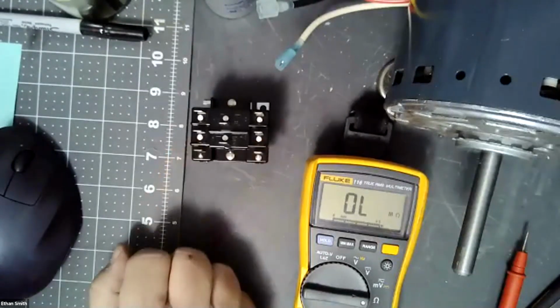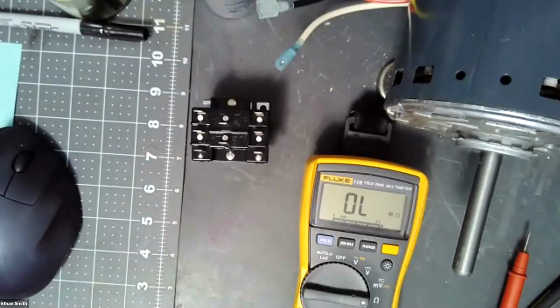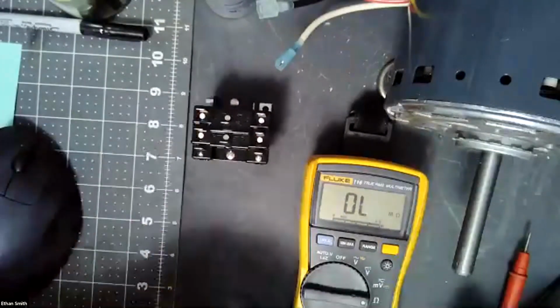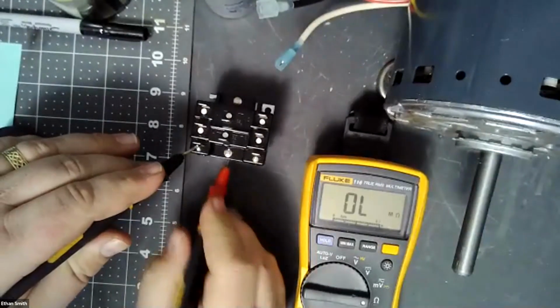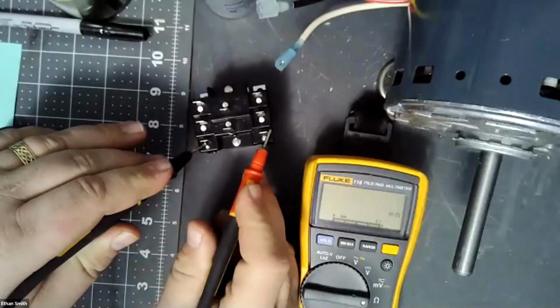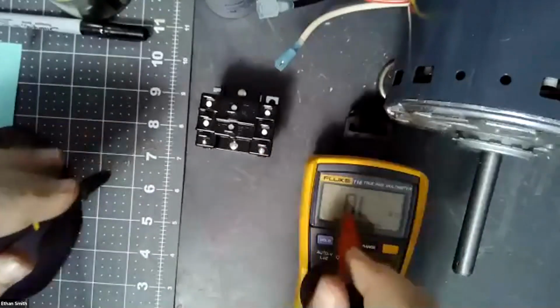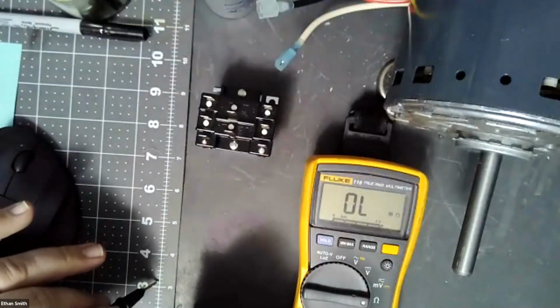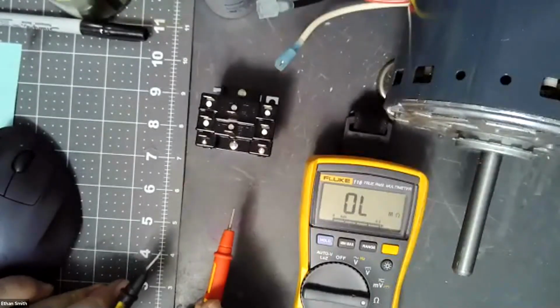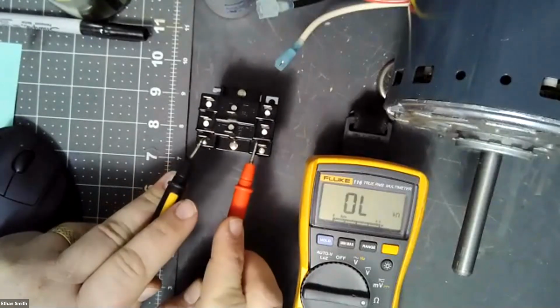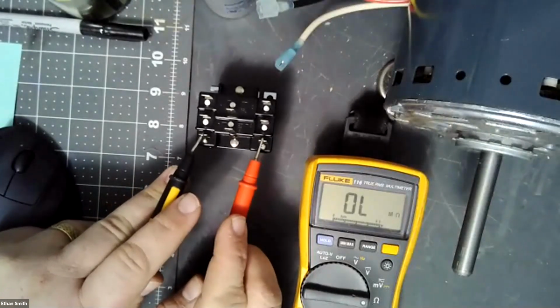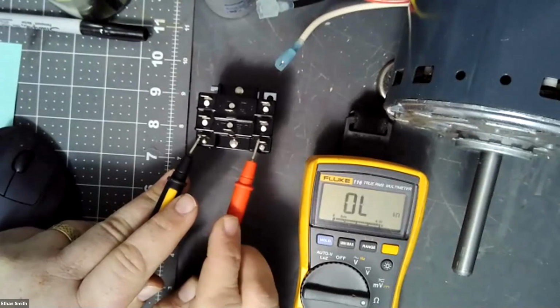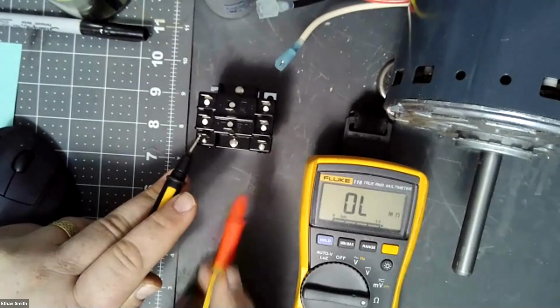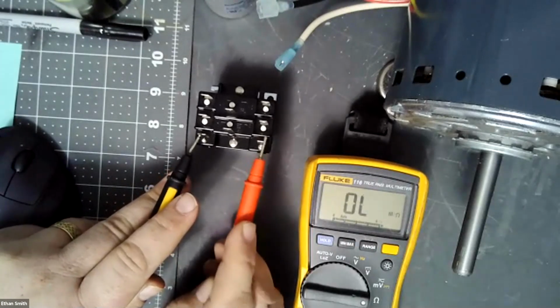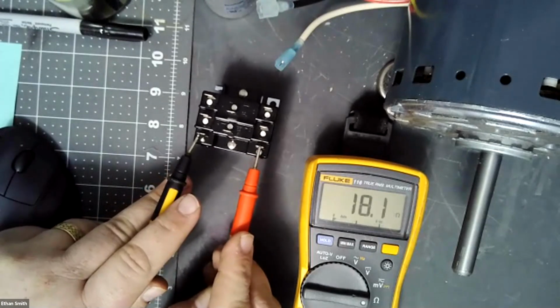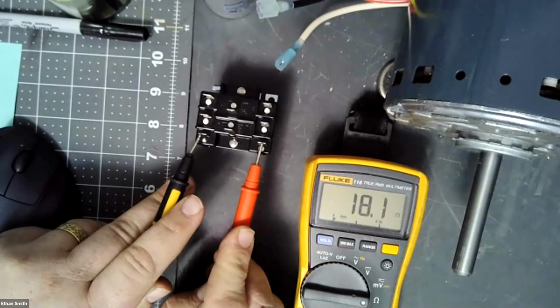Now you'll notice that there's no wires connected to this. Now, conceivably, if I had wires connected to my coil and I tried to take a resistance reading through it, even if my coil was open, it could find an electrical path back through the rest of the electrical circuit and get continuity somewhere else. And that's a little easier to see on the wiring diagrams later. But this is why when we're testing resistance through a device, we have to make sure that at least one side of that device is disconnected from any wiring. That way it can't find an alternate path around the circuit and give us a false reading. So when you're testing resistance, always make sure to unplug or unload the wires off of one side of your device or switch or coil or whatever it is.